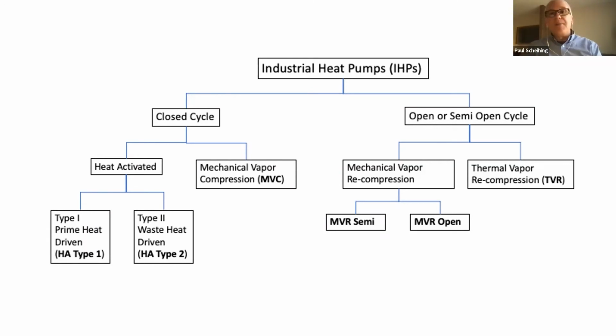But our report examined the full range of IHP types shown here, even the heat-activated heat pumps shown on the left. Those are pretty much in the minority, haven't been applied too much, but they can either be prime heat driven or waste heat driven, which makes them kind of interesting. They don't use as much electricity, but you'll see the economics currently aren't working as well for these types of heat pumps compared to the compression systems.